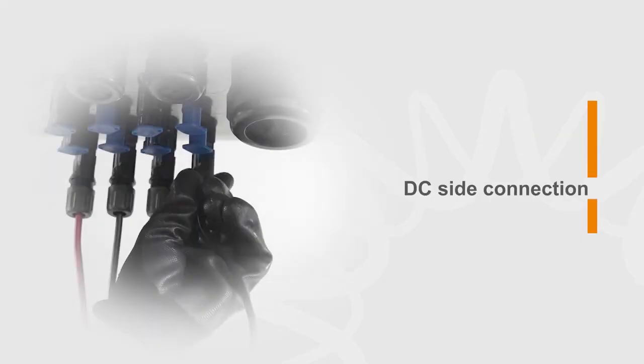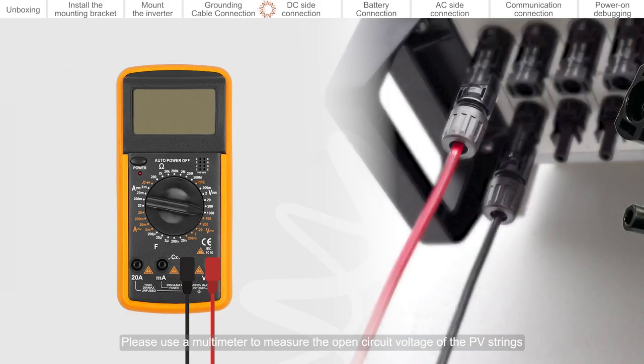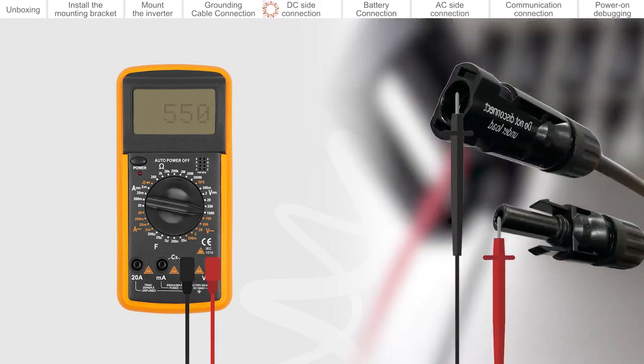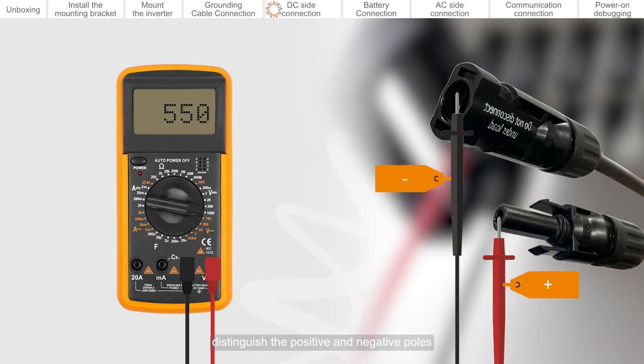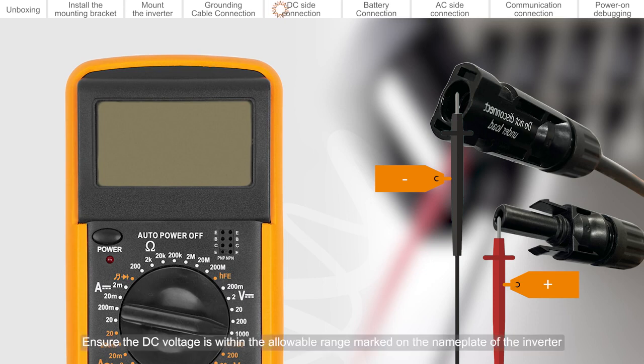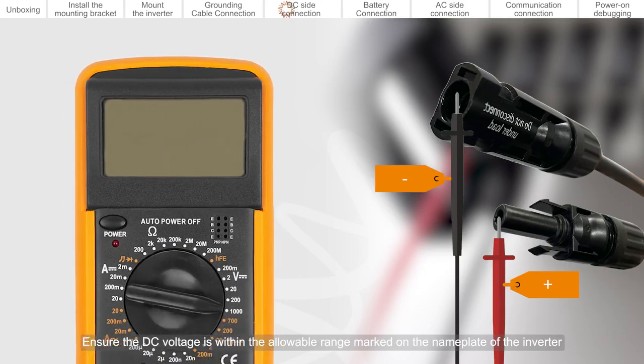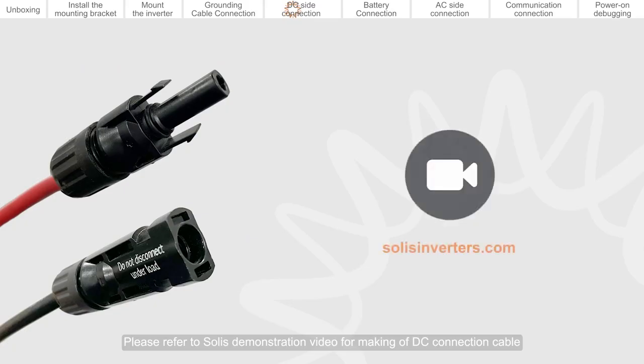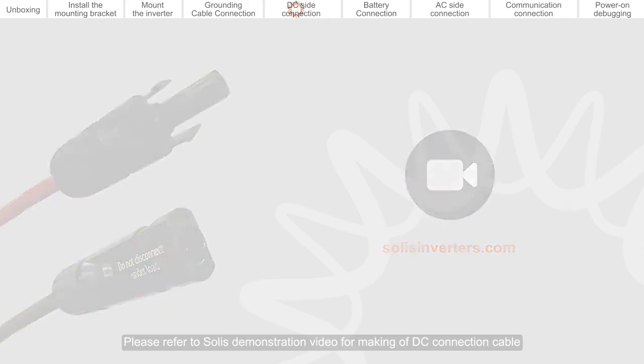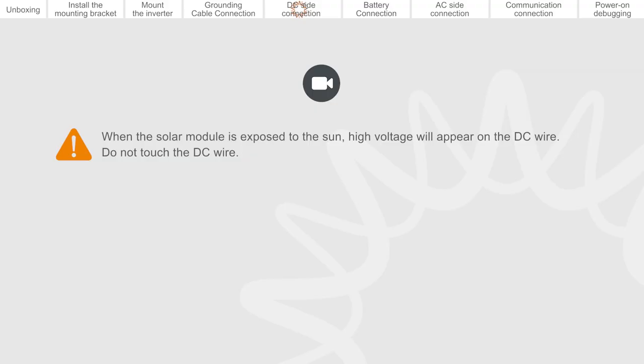DC side connection. Please use a multimeter to measure the open circuit voltage of the PV strings. Distinguish the positive and negative poles. Ensure the DC voltage is within the allowable range marked on the nameplate of the inverter. Please refer to the Solis demonstration video for making the DC connection cable. When the solar module is exposed to the sun, high voltage will appear on the DC wire. Do not touch the DC wire.